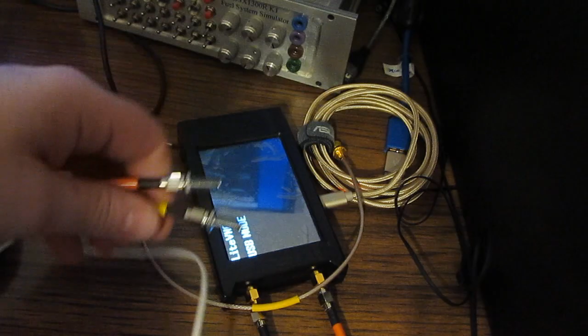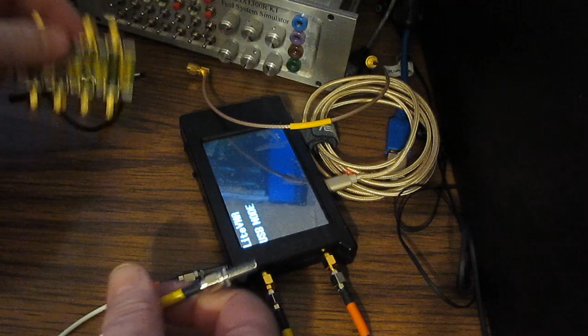In the previous versions of software, I didn't allow for the port extension to be adjusted unless the unit had been calibrated. That's no longer the case. We can go ahead and make that setting anytime we want. Let's just go ahead and enter 1000. And you can see now that's moved us over to roughly J70. Let's try going a little further, maybe 2000, about 3000. It's fairly close now to being matched.